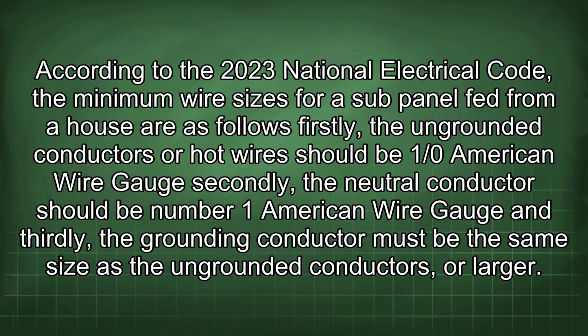According to the 2023 National Electrical Code, the minimum wire sizes for a sub-panel fed from a house are as follows. Firstly, the ungrounded conductors or hot wires should be 1/0 American wire gauge. Secondly, the neutral conductor should be number 1 American wire gauge. And thirdly, the grounding conductor must be the same size as the ungrounded conductors or larger.